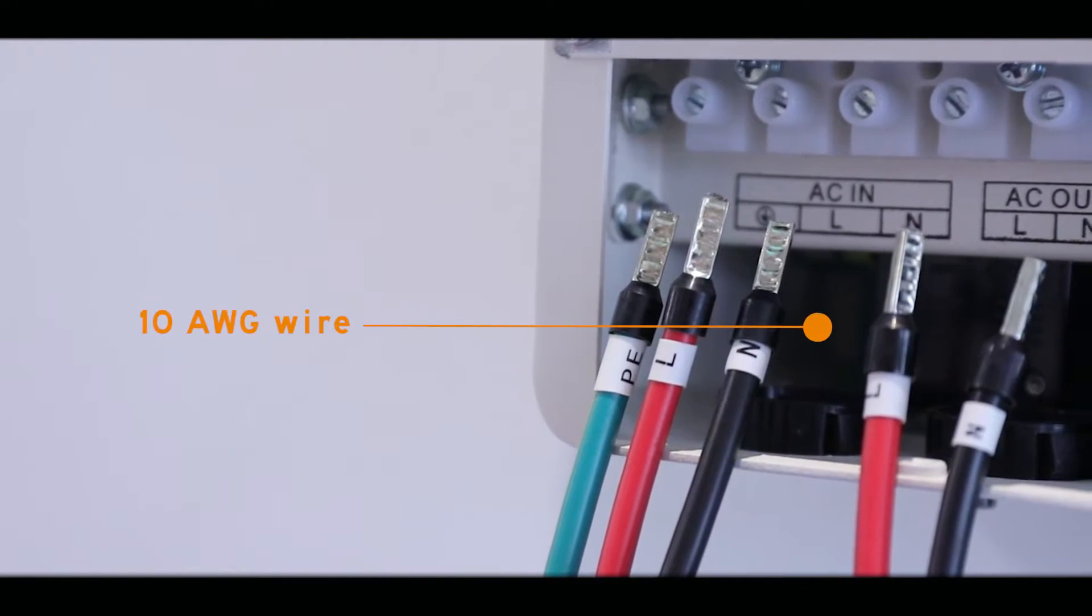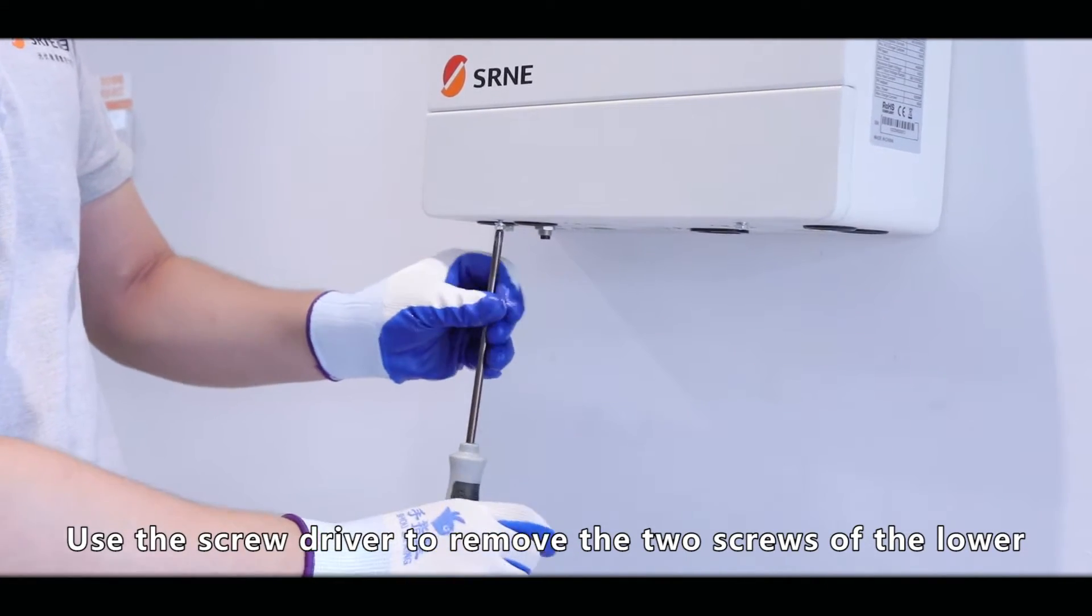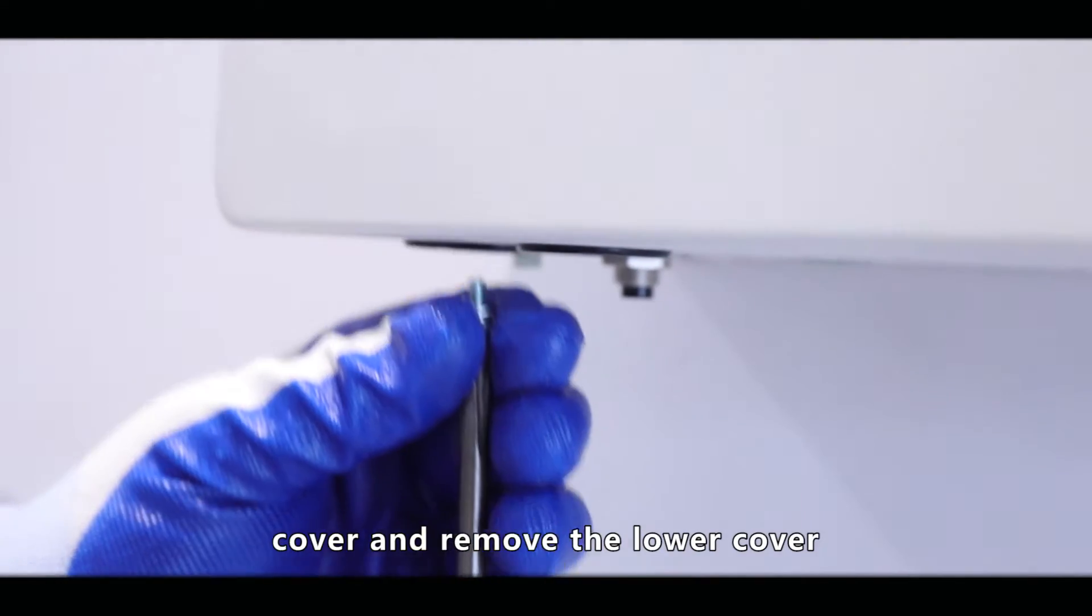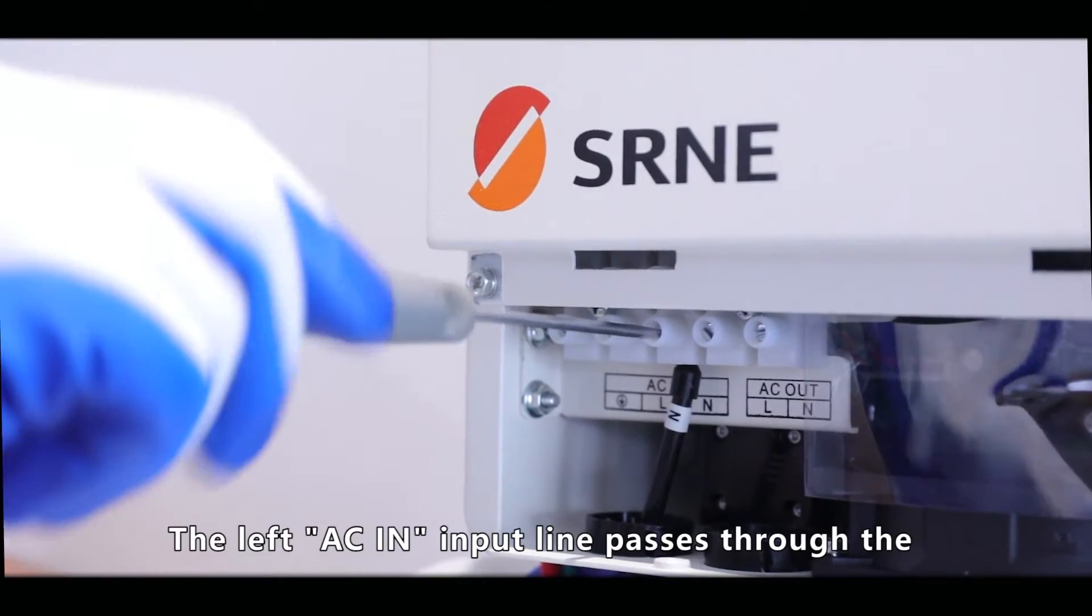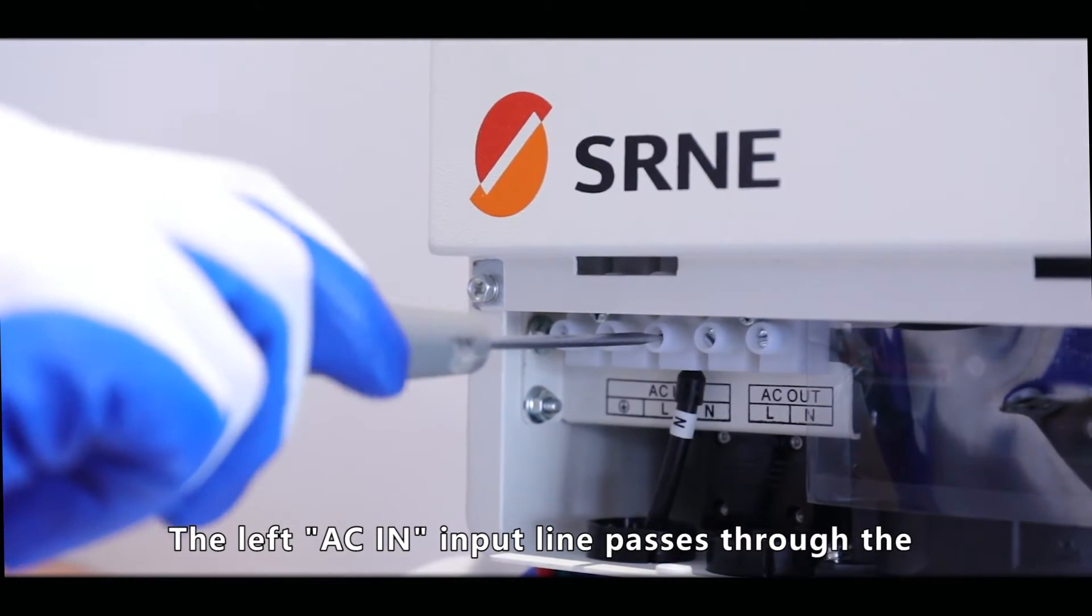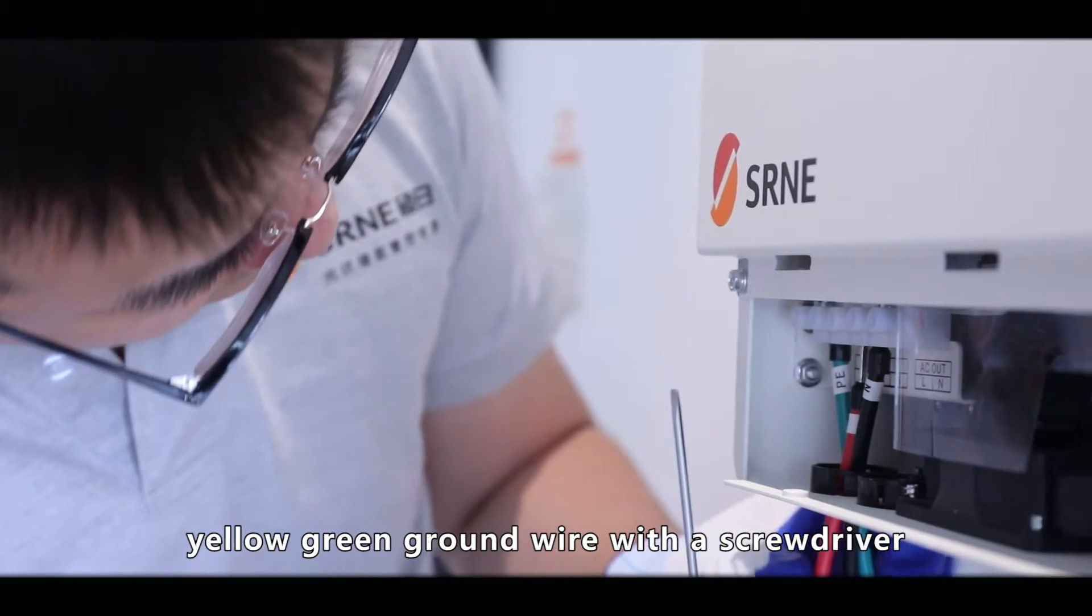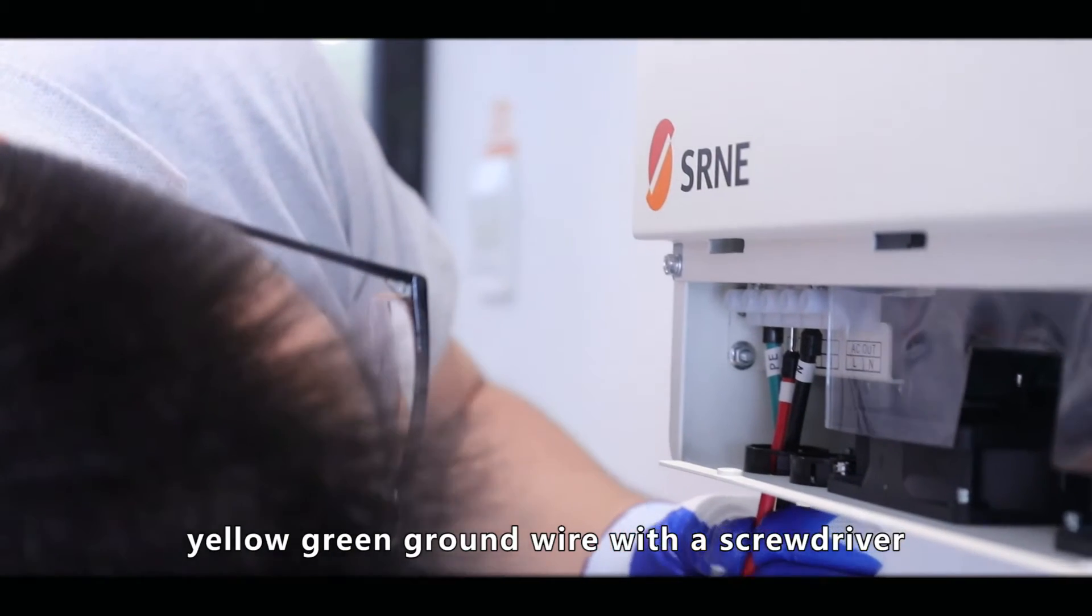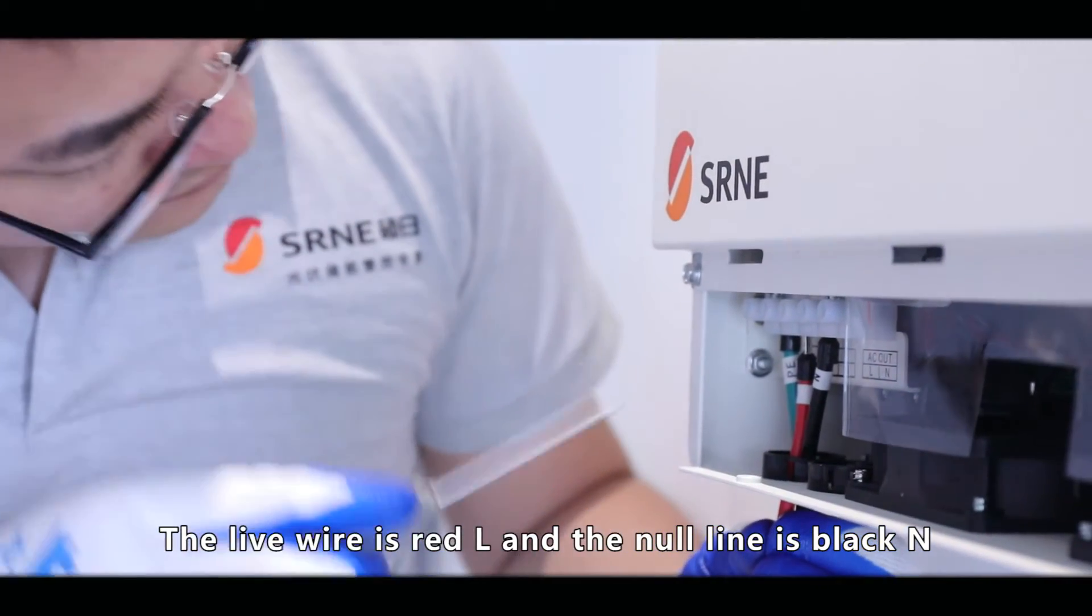Wiring: Use the screwdriver to remove the two screws of the lower cover and remove the lower cover. The left AC input line passes through the black guard ring and is connected to the yellow-green ground wire with the screwdriver. The live wire is red L and the null line is black N.